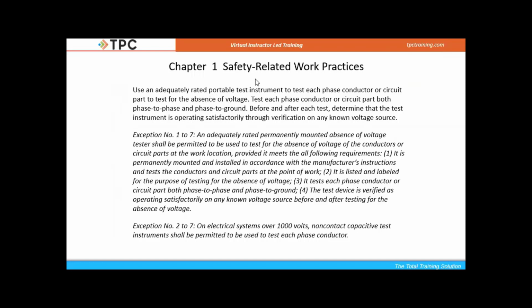Then it says, after we have the right meter in our hand, we're going to test each phase conductor, phase to phase. So that's A to B, B to C, A to C, and then phase to ground: A to ground, B to ground, C to ground. So there's 6 tests. And then it says before and after each test, we've got to make sure that meter is working properly. So before I even start phase to phase or phase to ground, I'm going to test my meter on a known voltage to make sure that my meter is working just perfectly. And then when I'm all done, I'm going to test that meter again on a known voltage. I'll give you an idea why this is extremely important.